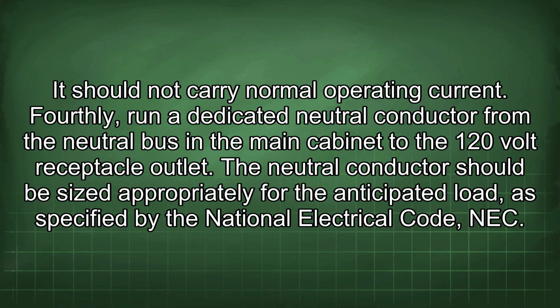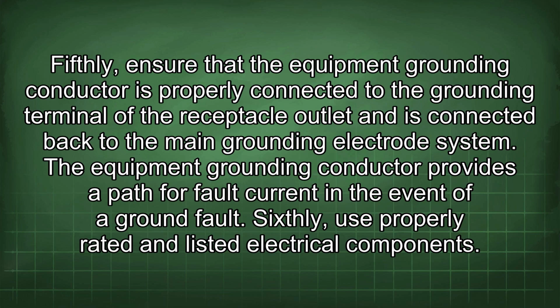Fourthly, run a dedicated neutral conductor from the neutral bus in the main cabinet to the 120 volt receptacle outlet. The neutral conductor should be sized appropriately for the anticipated load, as specified by the National Electrical Code (NEC). Fifthly, ensure that the equipment grounding conductor is properly connected to the grounding terminal of the receptacle outlet and is connected back to the main grounding electrode system. The equipment grounding conductor provides a path for fault current in the event of a ground fault.